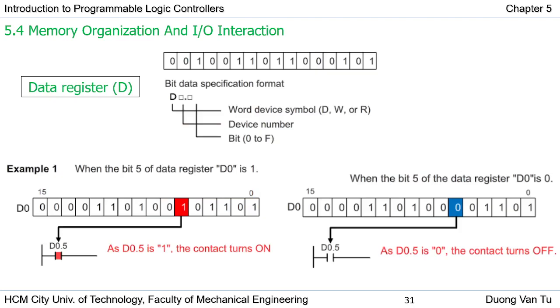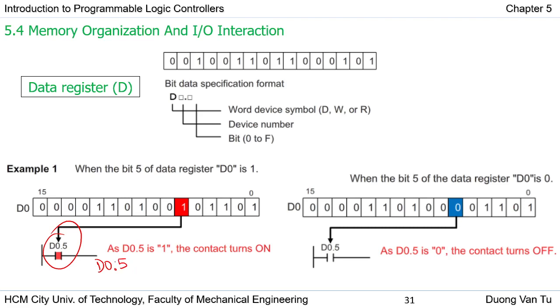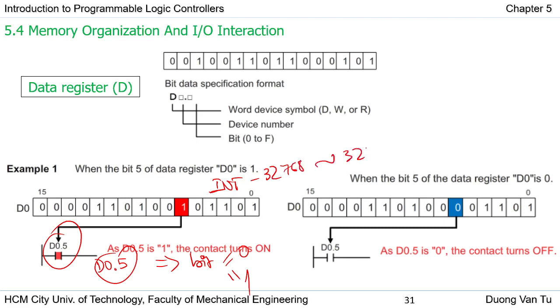Now we can see the data register. For the data register, you can access the whole register or you can access an individual bit. For example, when you want to access bit number 5 of register D0, you write it in the format D0.5. This bit value is only 0 or 1, whereas the full register has 16 bits with data range from -32,768 to 32,767.